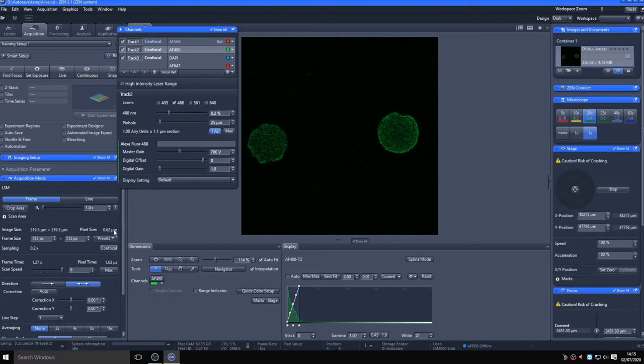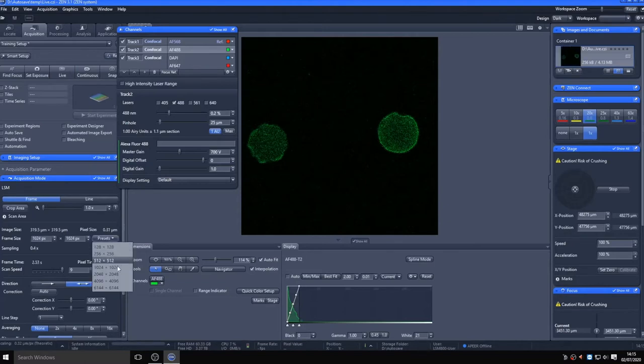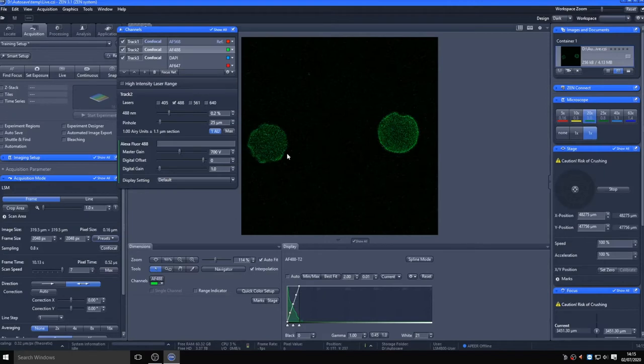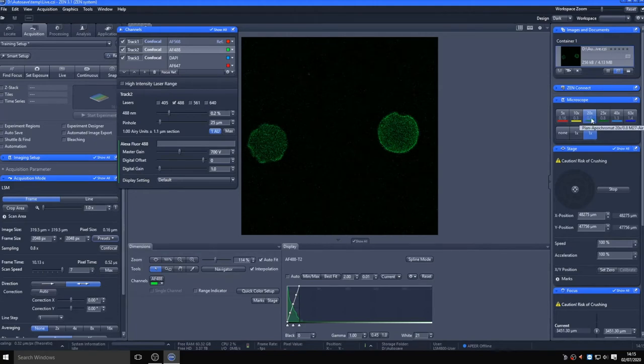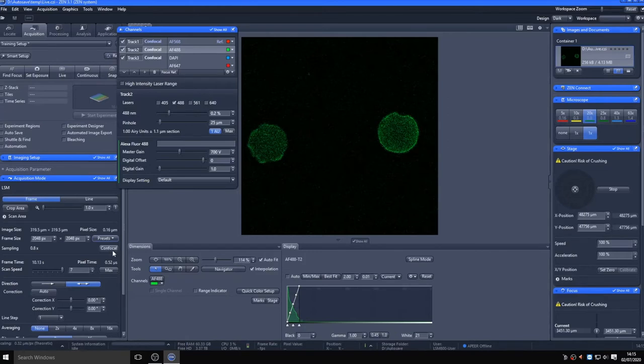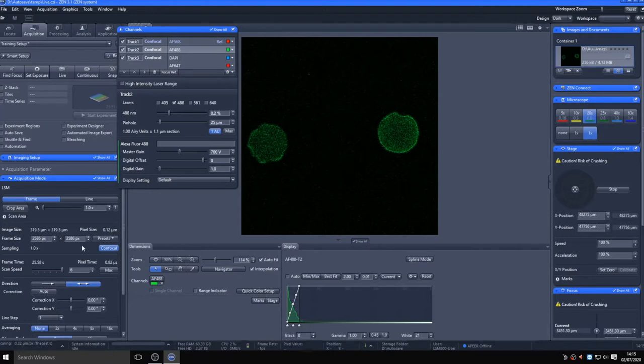The acquisition panel is also where you determine the size of each image. Live defaults to 512 by 512 pixels, no matter what you set in this panel. However, when acquiring an image via Snap or Start Experiment, the settings you enter here will be captured. The continuous button will also use current settings. You can choose default frame sizes to change the pixel size across your image field of view, or you can use the confocal button, which will set the XY sampling at the theoretical resolution, which is known as Nyquist sampling. This is set to the limit of the lens numerical aperture and wavelengths imaged.